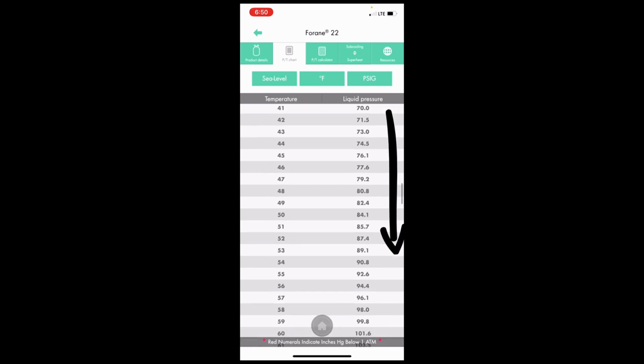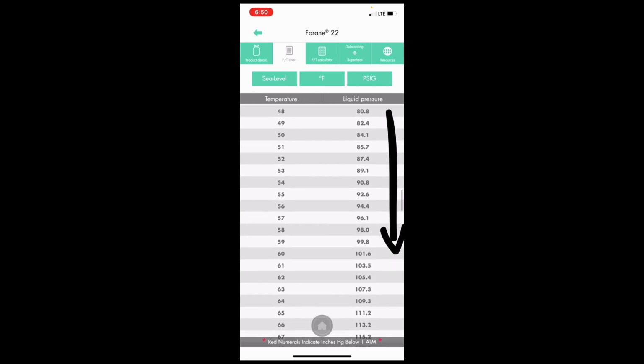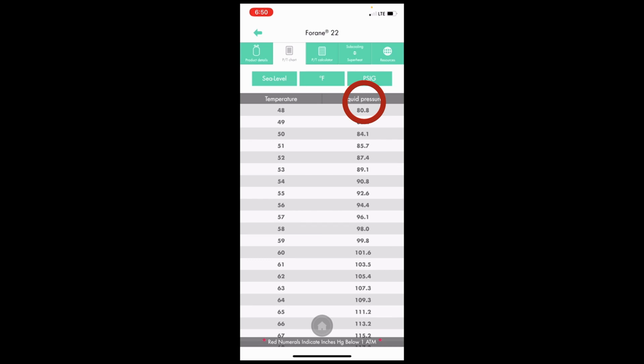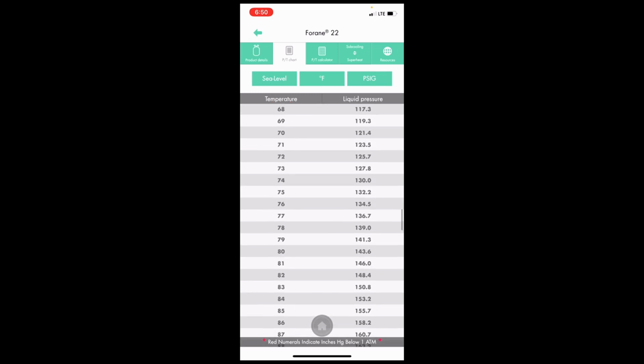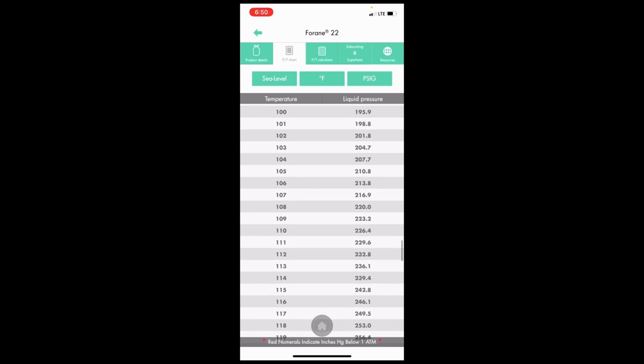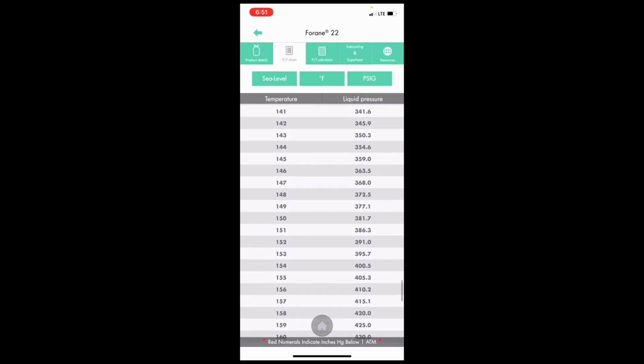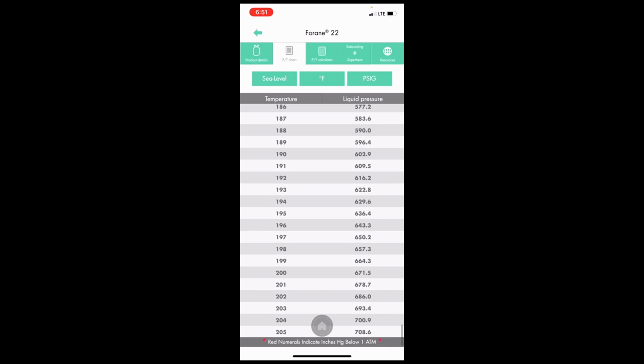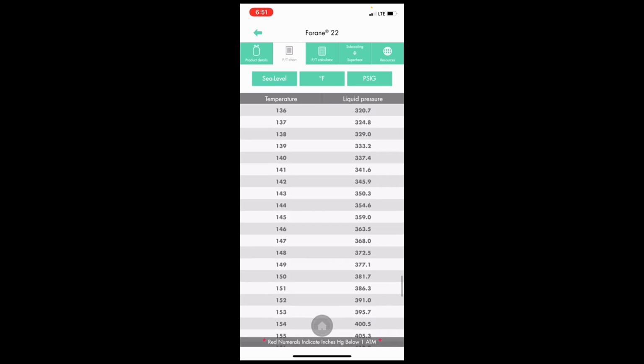As your pressure went up, let's raise the pressure to say 81, my evaporator temperature would be boiling at 48 degrees. I have a 48 degree saturated temperature. On our condensing unit, let's say our outside condensing coil, let's say our head pressure was 196 psi gauge, our saturated temperature would be 100 degrees Fahrenheit. And we could go on and on and on to this list, but it's just got tons and tons of great information for us to use.